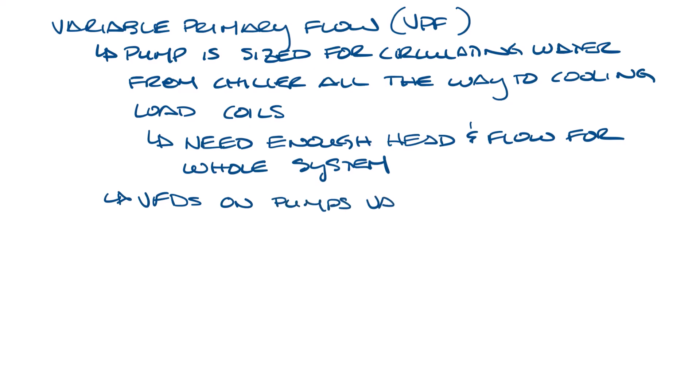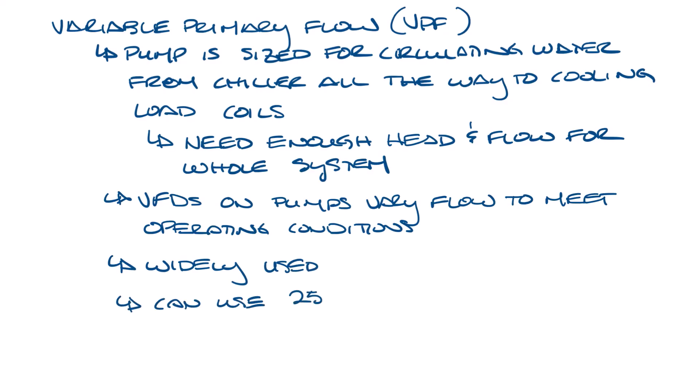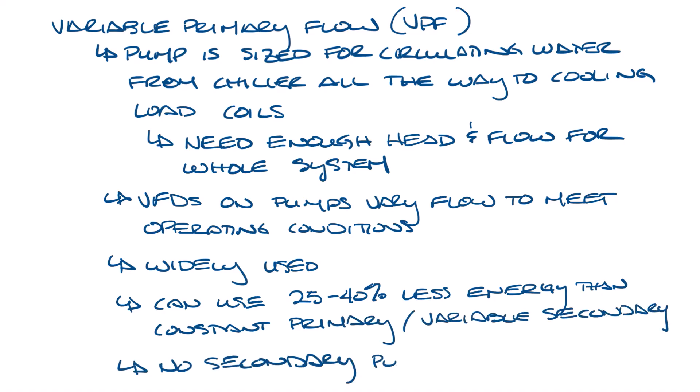VFDs on the pumps vary the flow within the system to meet the operating conditions. This system is widely used. It can use 25 to 40 percent less energy than the constant primary variable secondary pumping system. And since there's no secondary pumps, the first cost is relatively low.